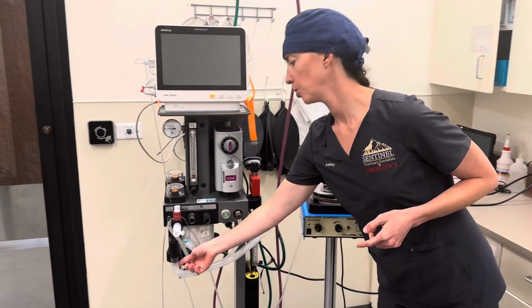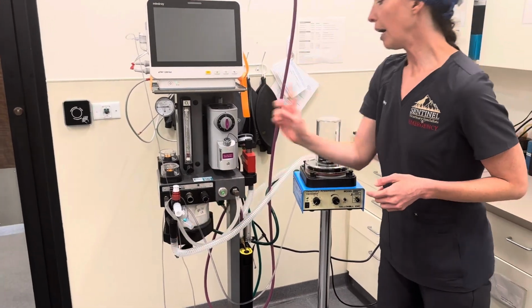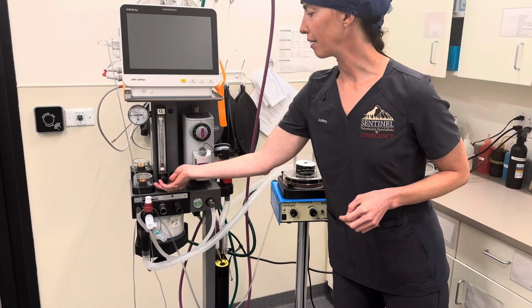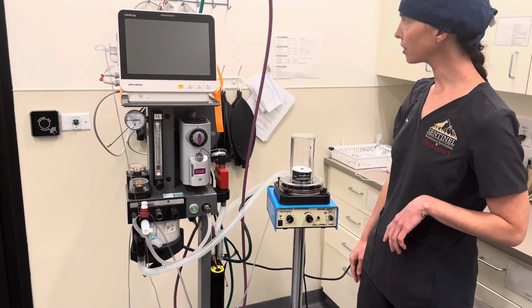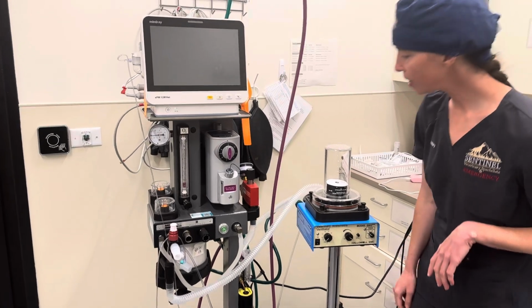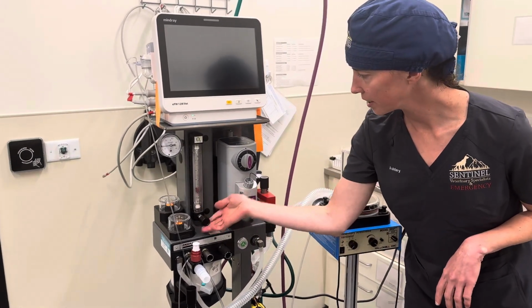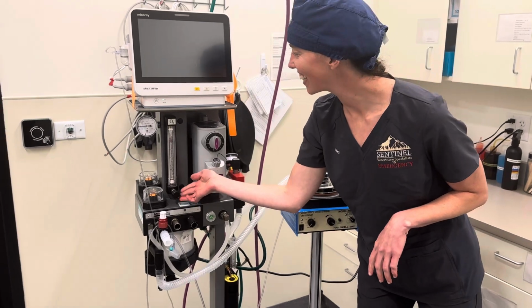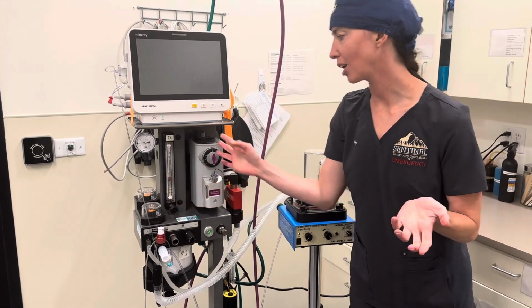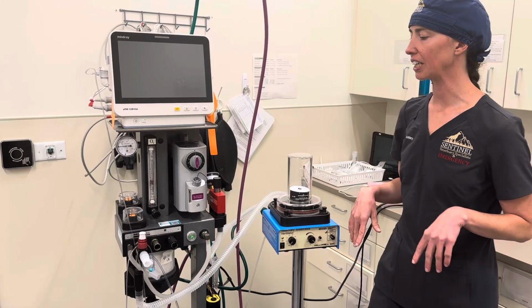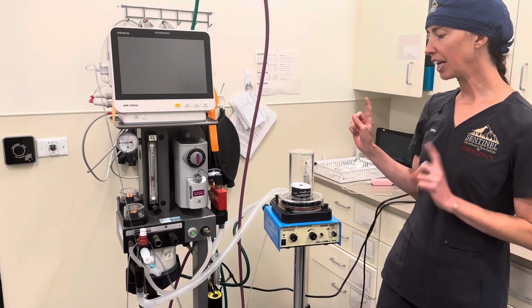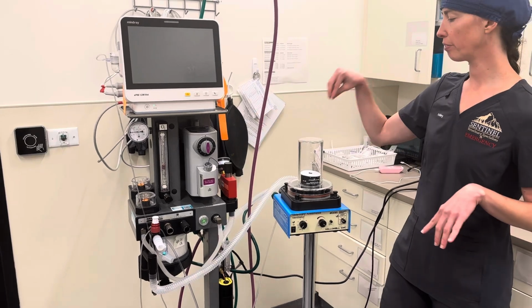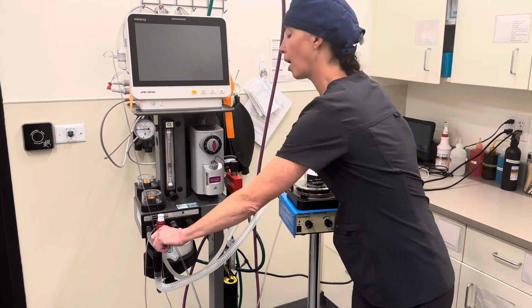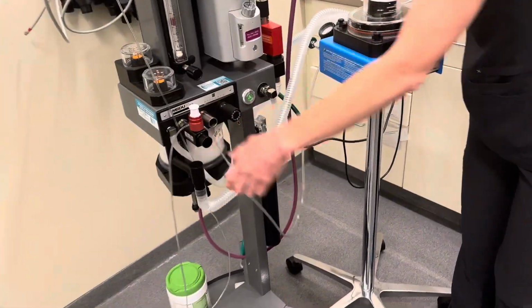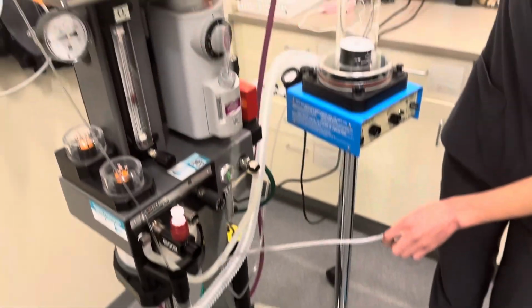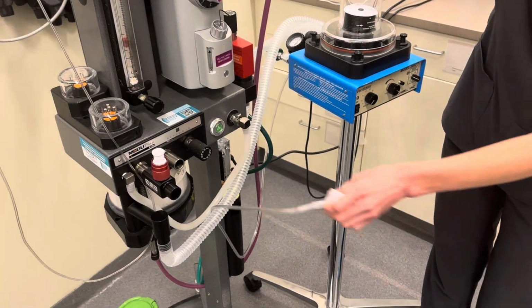So we've got it hooked up to where our breathing bag should be. We have our pop-off valve closed. We're going to have our oxygen on. Why isn't my oxygen on? Oh, there it is. It's just tiny. I didn't turn it enough times. So you're going to have your oxygen on, and let's say it's on 1 liter per minute, or wherever you're going to set it for your patient. And then the other thing to make sure you have on this machine, for this machine to work, is your pressure reader. So this is your capnograph line, which we're going to leave up here because we don't have a real patient.